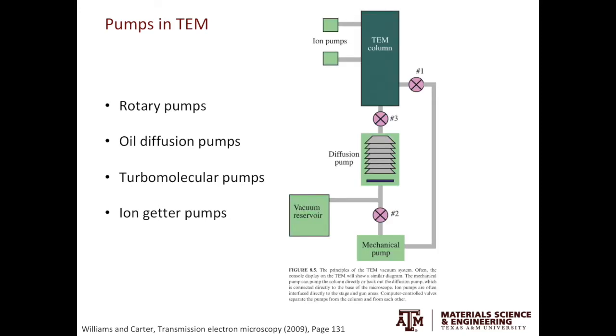To give you a big picture and to put all the pumps together — we start with the mechanical pump or the rotary pump. It will reduce the pressure in the system. Once the vacuum is okay, the diffusion pump will be turned on. When a better vacuum is achieved, the ion getter pumps will kick in to reach an even better vacuum. Let's look at how these pumps work one by one.